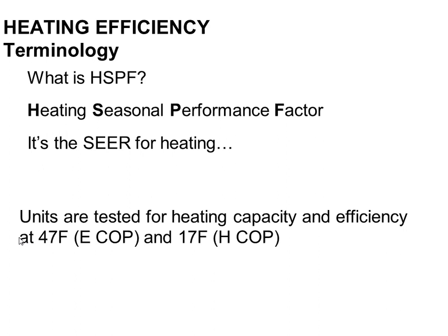So heat pumps, air source heat pumps, as well as water source heat pumps, are rated at 47 degrees. The reason they are rated at 47 degrees is because the heating content of the air at 47 degrees is very similar to the cooling needs at 95 degrees, right? We already test condensing units at 95, so then we retest these heat pump versions at 47 to see what their capacity happens to be. It's a really nice test because it's basically the same deviation from set point compared to outdoor temperature as in the cooling season. So 47 is basically 95. However, in terms of operation, people want to know what's going to happen when it's colder out too. So heat pumps get a second rating point at 17 degrees outside air. There's a 47 degree rating point and a 17 degree rating point for a heat pump, whereas an air conditioner would just have 95 degrees.